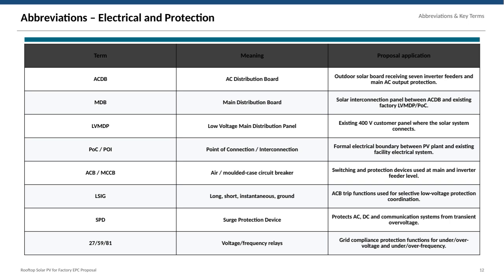The LVMDP is the existing 400-volt panel where the solar system physically connects. The point of connection, also called POC or POI, marks the formal electrical boundary between the PV plant and the facility's existing electrical system. For protection, we use devices like the ACB or MCCB, air or molded case circuit breakers, at both the main and inverter feeder levels to ensure safe switching and fault protection. The LSIG functions on these breakers allow for selective protection coordination by detecting long, short, instantaneous, and ground faults.